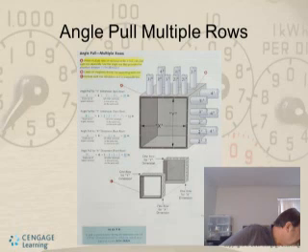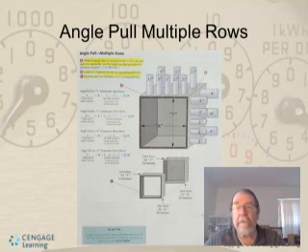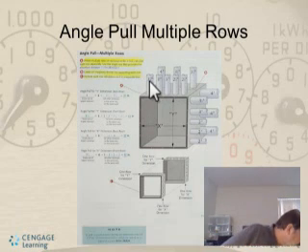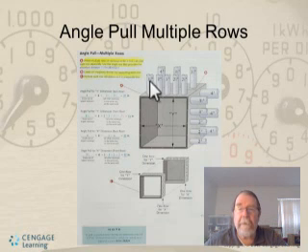So if you're looking at the example for the angle pull, the first one, the front section is 3.5 by, so you got a 4-inch conduit. That's the back row they're doing, and back top. This calculation right here is working on this row back here. Okay, so they're taking the 4, multiplying it by 6, and then adding these two together, and it gives you that. Then this one should be taking the largest one here, which is your 3.5, multiply it by 6, and then add all these together to give you this number.